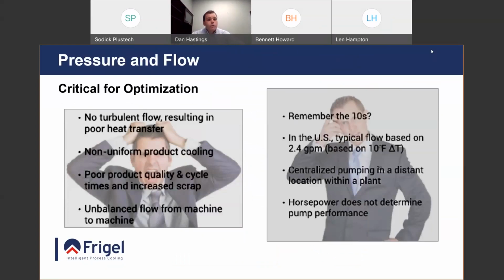So some things to think about if you are having mold cooling issues. Maybe it's due to low flow, too many connections. I put the slide here to make you think about what my process is and what I am seeing issues with. And by understanding that, I know I keep on repeating this, flow is going to be a benefit for your process. And to get flow, you need to make sure that you have the correct pump. By going from a 3/4 horsepower TCU to a 3 horsepower, that might be great. It's going to be a bigger pump. It's going to provide more flow.